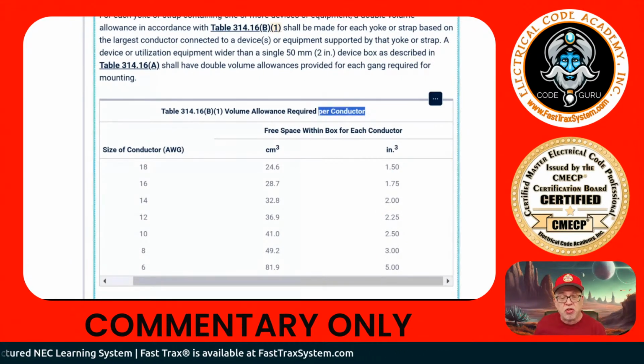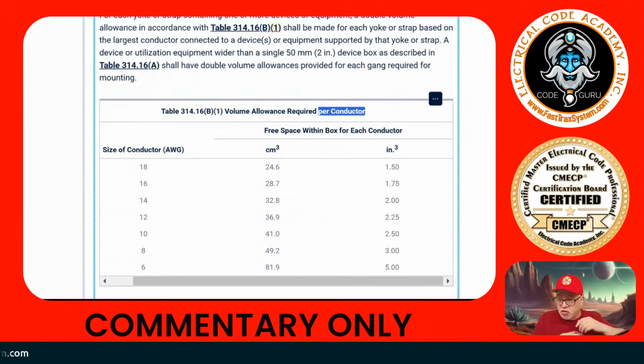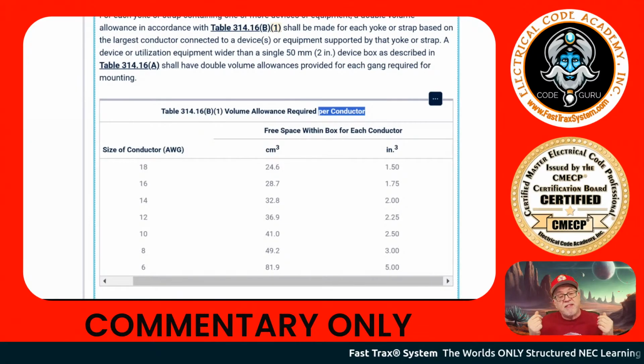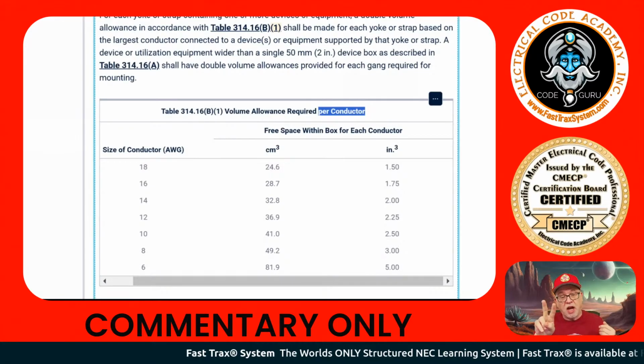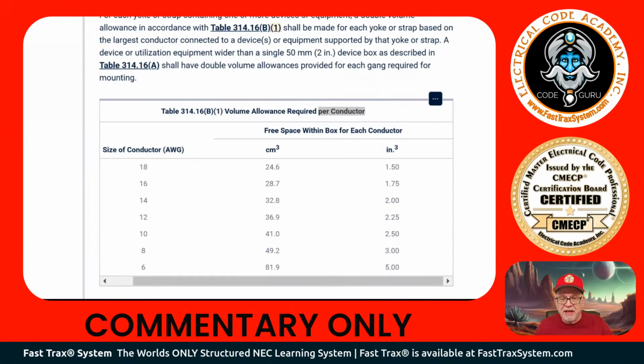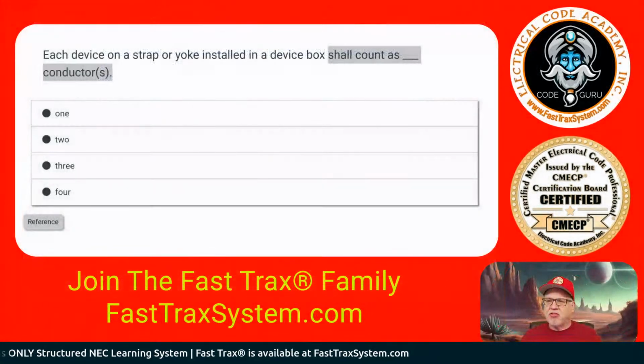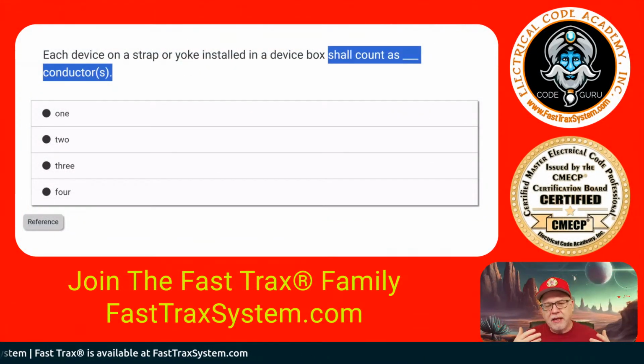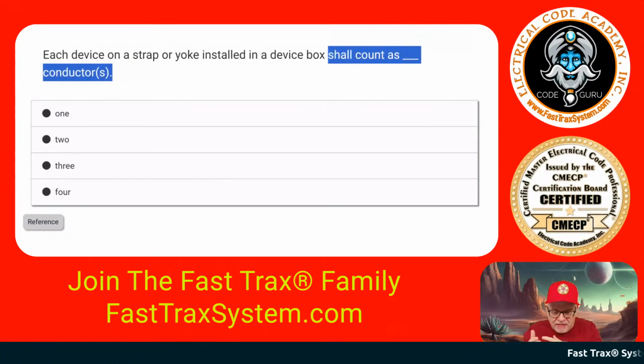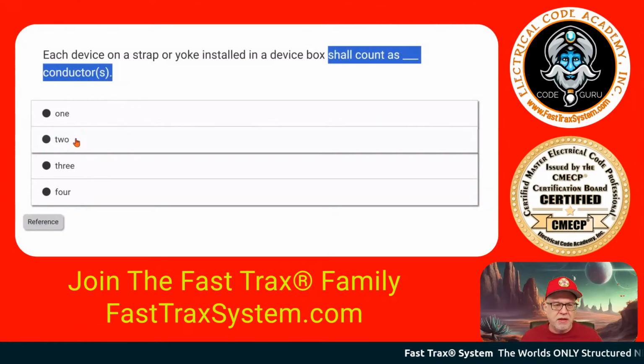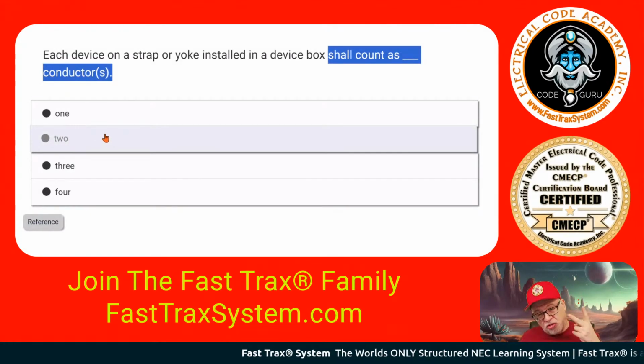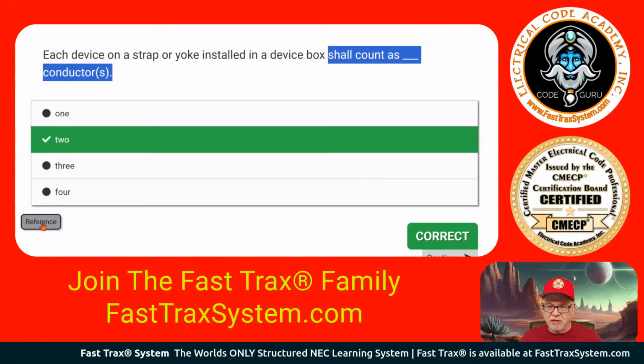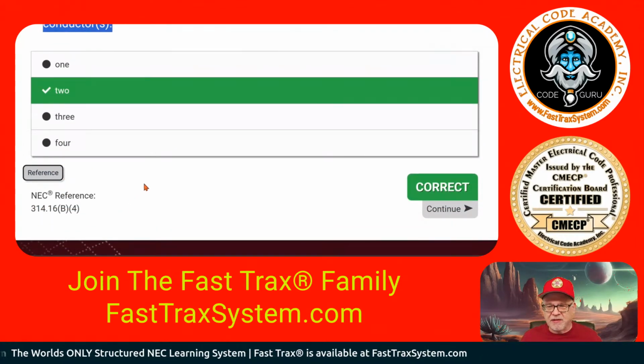Be careful. It's all about the verbiage. It's all about how you read it. And you have to know that a double volume simply means 2 conductors. 2 conductors, if it was 12 gauge, it would be 2.25 each. If it was 14, it'd be 2.00 each. But it still represents what? 2 conductors. Be very careful in the question. No, it's not a trick question. It's just trying to let you read it and not get lost and say, wait a minute, they didn't give me the conductor we're talking about. That makes a difference. It does not make any difference in this question because a double volume count equates to 2 conductors. And that's the answer. And there's your reference, 314.16(B)(4).